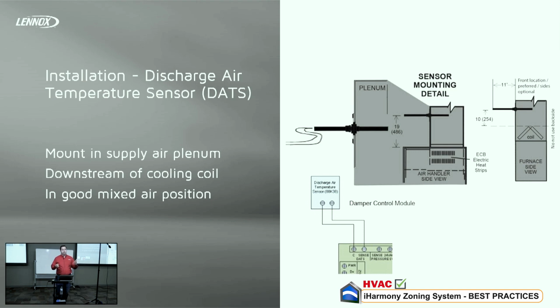And there'll be times where that discharge air sensor is in kind of a cold spot, a dead spot corner of the plenum. Sometimes that happens. It used to be we'd tell you to put it halfway into the plenum, but we've noticed that sometimes that can be a little bit of a dead spot. And sometimes it can delay cranking up the CFM and can cause a nuisance limit trip.